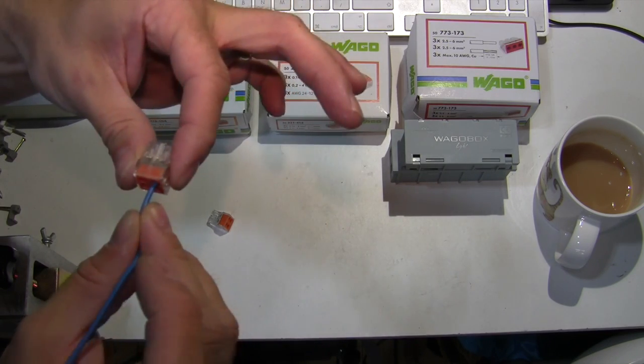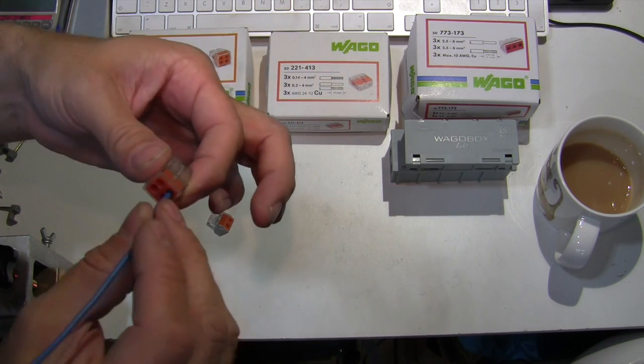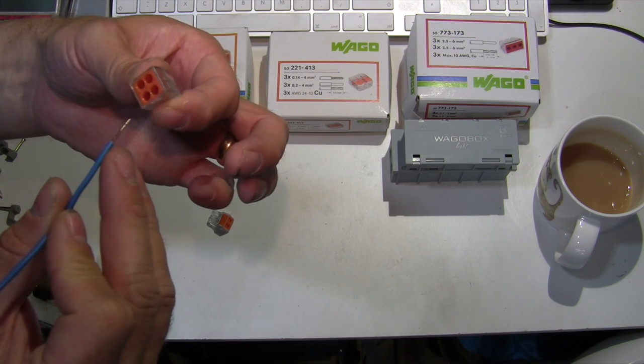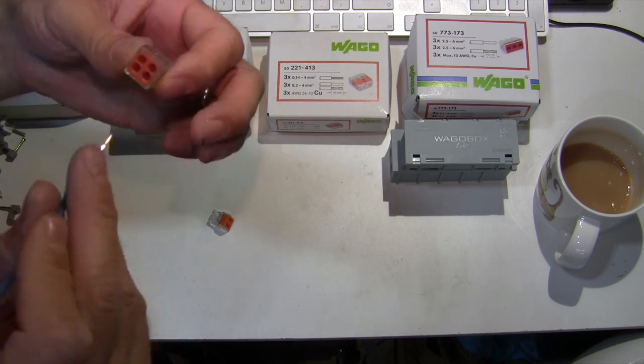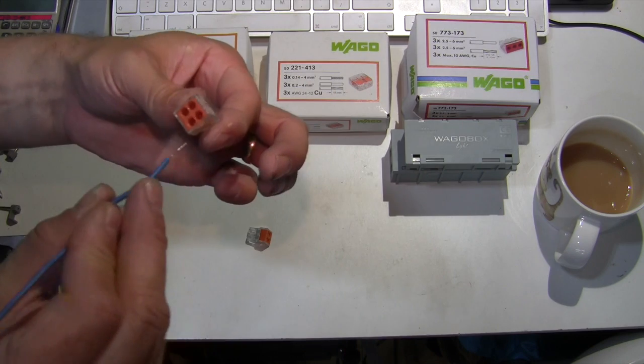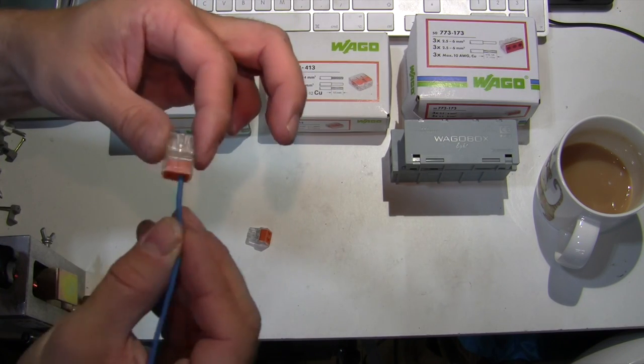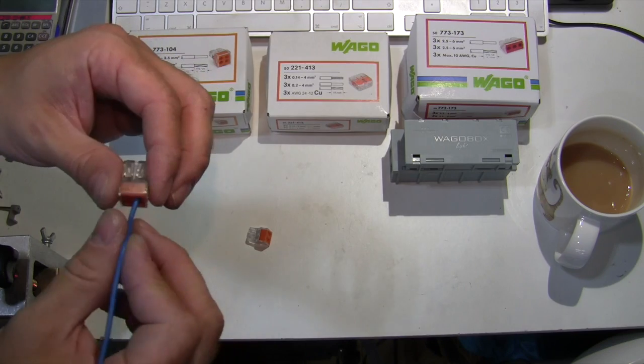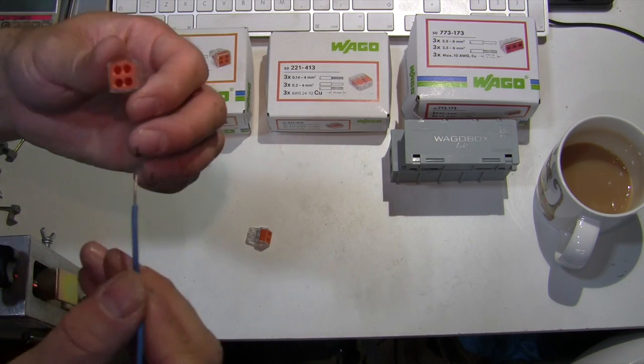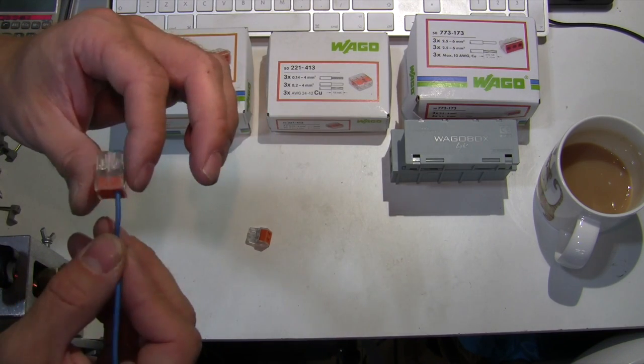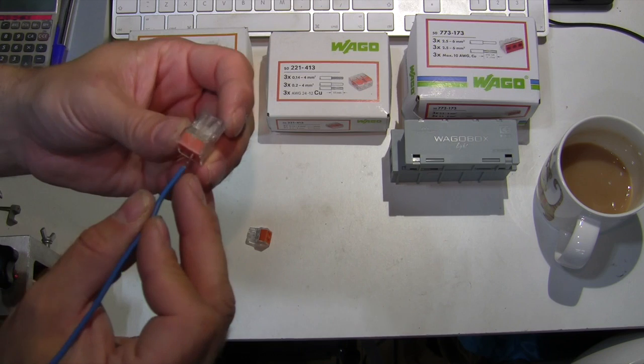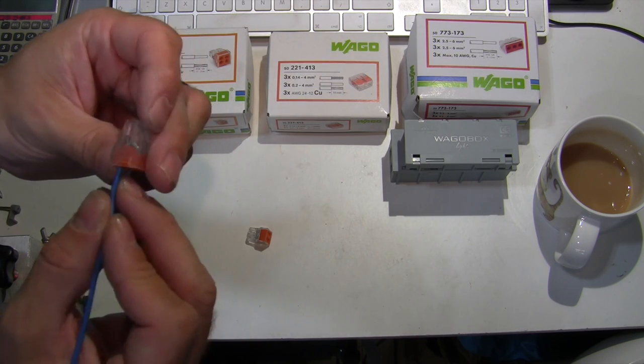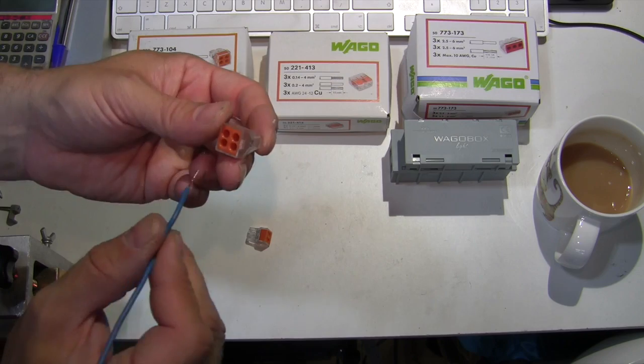So that's what the fault was. It was this supposedly maintenance-free style of connector, which has failed. Now, I don't know. It wasn't me who actually installed it. It was one of my colleagues. I don't know whether they fitted a wire in and then had to take it back out again for whatever reason and if that's left it damaged inside. But that doesn't happen with the Wagos. You can take it out and that connector is perfectly reusable. For whatever reason, the spring mechanism in this has failed and left it with a loose connection. And that loose connection didn't manifest itself at the time that light was put up. The test results came out okay. The lights have been operating for the past few weeks and for whatever reason it's now decided to just pop overnight. I don't know if there's been some external influence like a vibration or a bit of localized heat that's caused it to pop open further and to finally fail or what. But there we are. That's the fault.